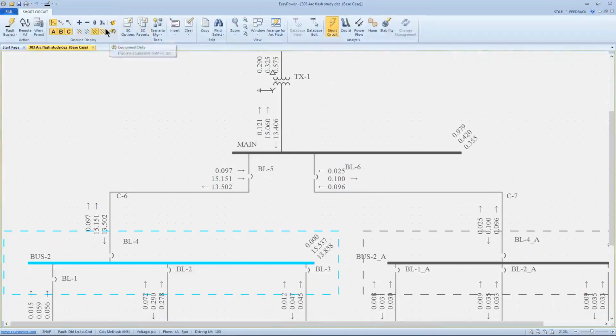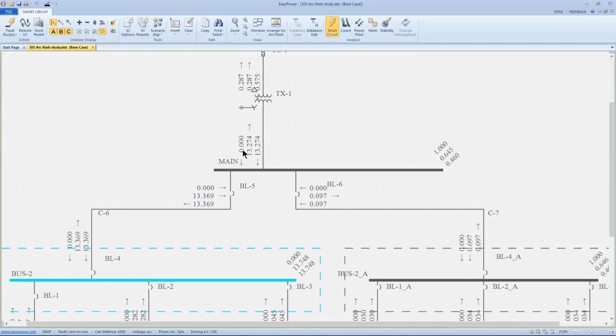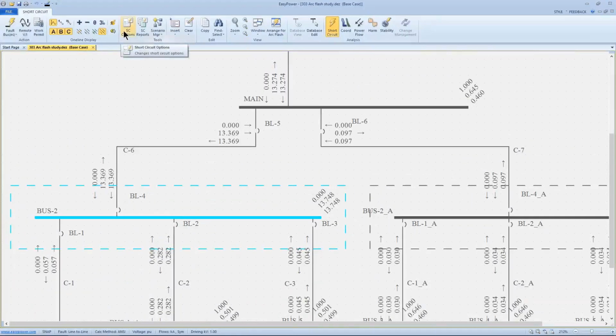And then finally, line to line, where we have no ground interaction, so we only see the two phases between, in this case, B and C. Now, it's worthy of note. What we're showing here is the current in line and then the per unit voltage on the bus itself. And so this is the voltage on phase A, but since the fault is between the other two phases, they will be at reduced voltage. And consequently, there's no current on phase A. Now, if that's too much information, we can always reduce the display of the remote buses. So those are the application of the short circuit currents on symmetrical and asymmetrical faults themselves.